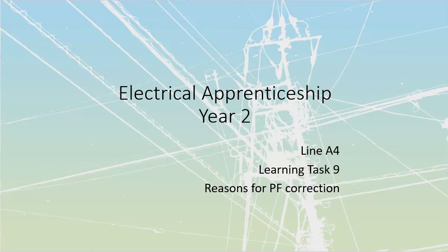That was it. So when they left their large transformer, a couple hundred kVA transformer because they had some 208 volt irrigation pumps inside there, as well as some of the 600 volt ones, as soon as they left that thing idling along at a couple hundred kVA, developing only a few small watts, they had a ridiculously low power factor. And he ended up with that $3,000 bill, roughly.